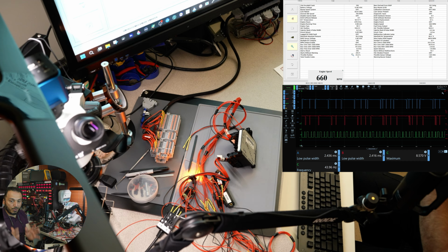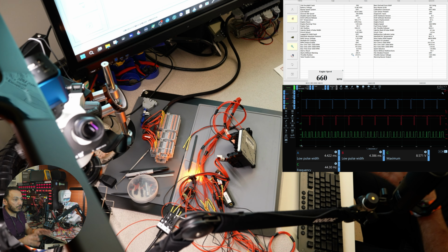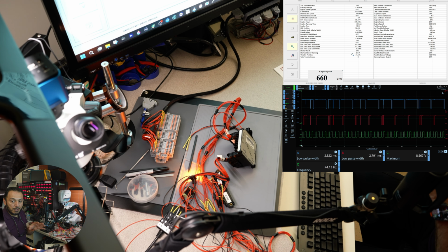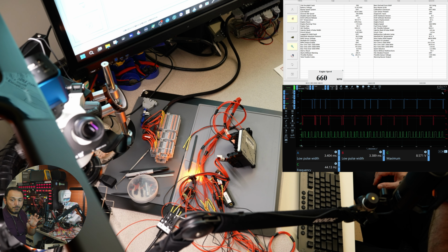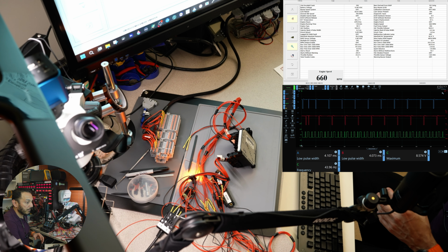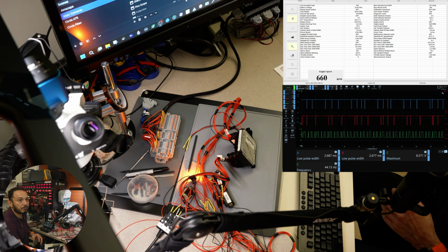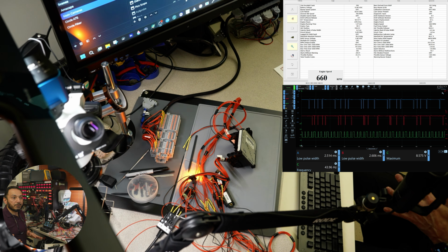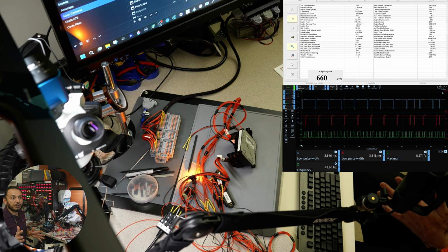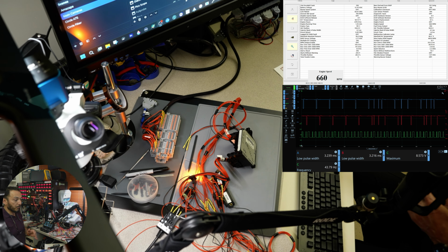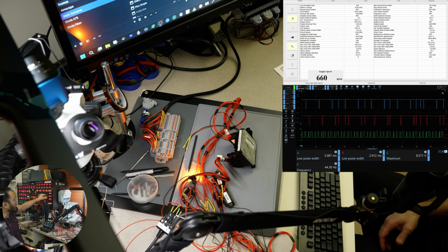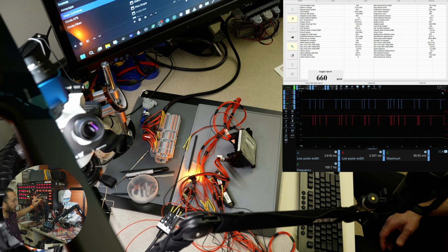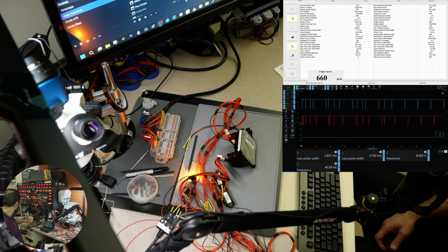So if I connect another computer, which I'm going to do right away, let's capture into your brain that the green channel is at 8.5 volts. Let me make sure I can read that with you guys. So we got 8.5 volts and 44 hertz on that signal, and that is exactly what the computer is sending out onto the RPM. I'm going to unplug my channel from that RPM signal so you can see it's indeed reading a real-time signal coming from the computer.